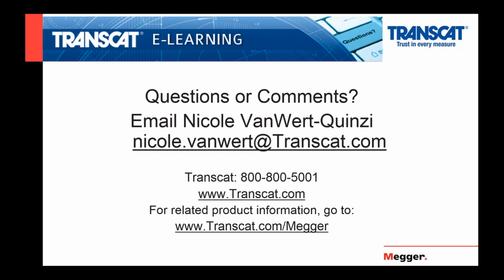Can you over-equalize or equalize too frequently? Yes, absolutely. You can cause excessive heating. Whenever doing an equalization charge, always, always, always do it per the battery manufacturer's recommendations. And then how long after a load bank test is completed should an equalized charge be started?